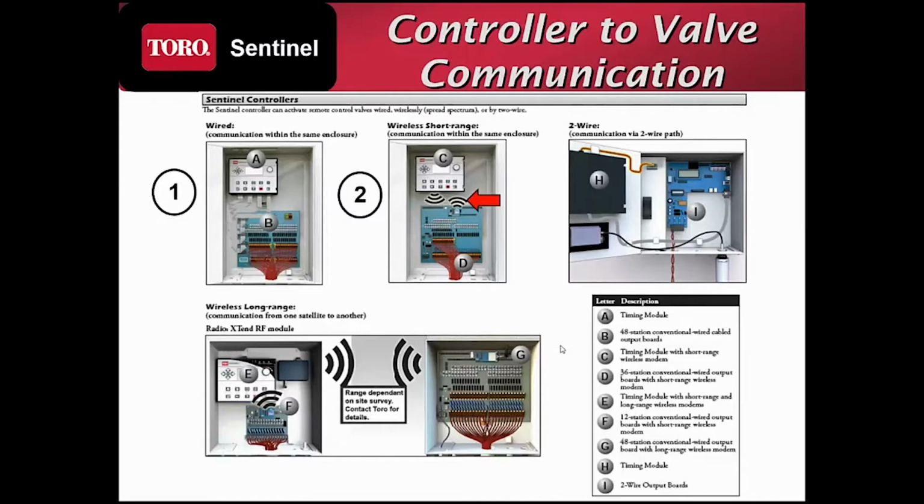Then we get into option 3. On option 3, we're doing a similar communication. Now, I should mention that the radio signal that we're transmitting in this wireless is what's called spread spectrum. On item 3, we're communicating over what's called 900 megahertz is the frequency. On your UHF radio, unless you've got a government site, you're communicating between 450 and 470 megahertz. On this spread spectrum, we're communicating at 900 megahertz.